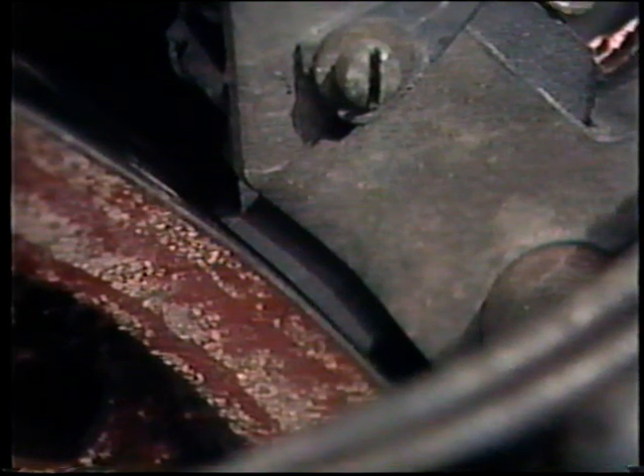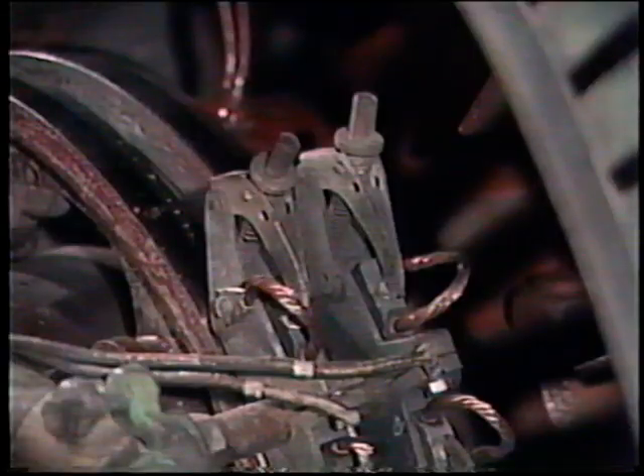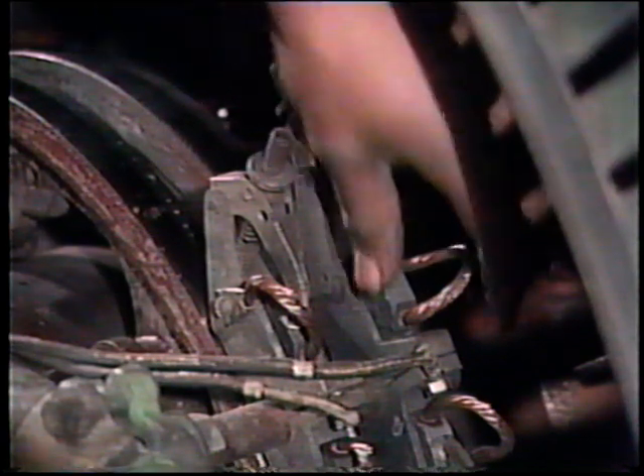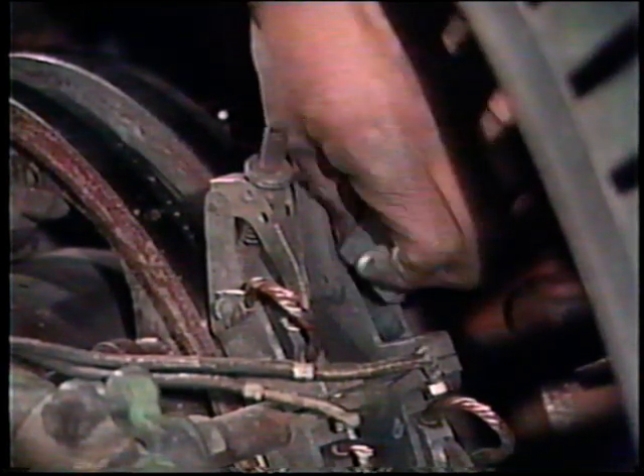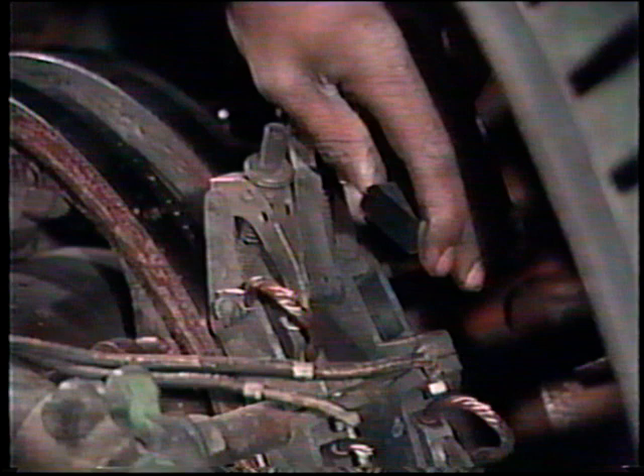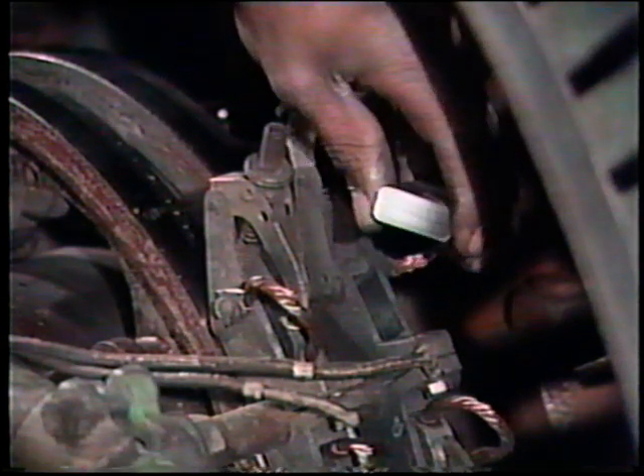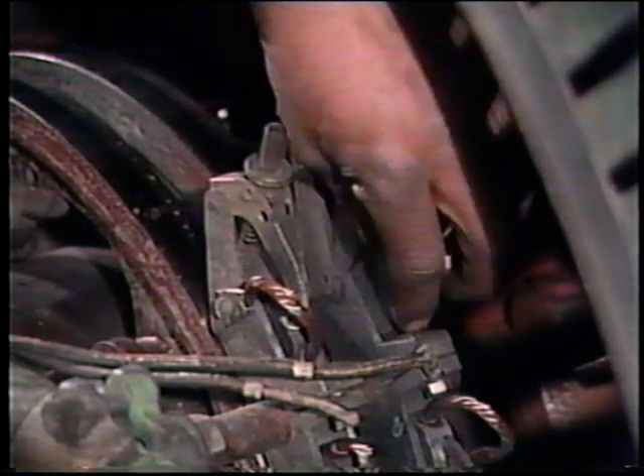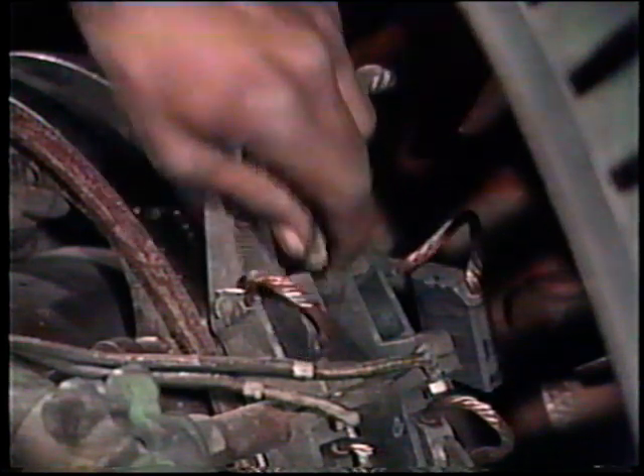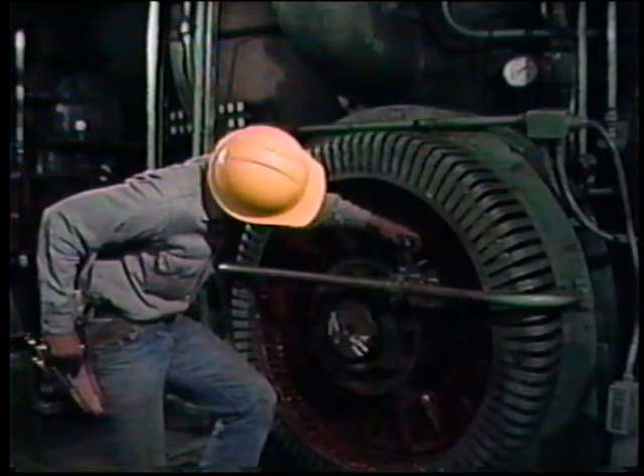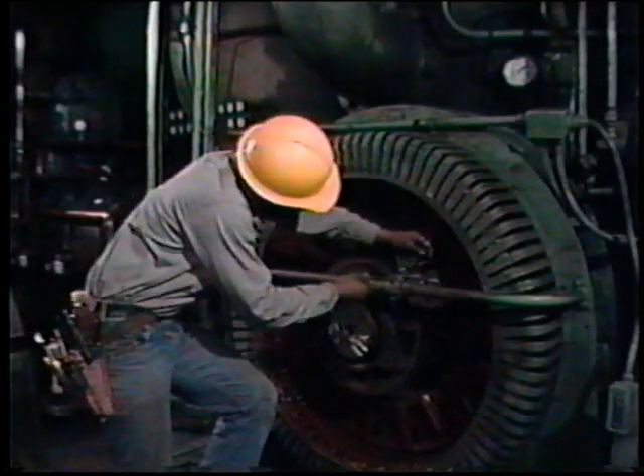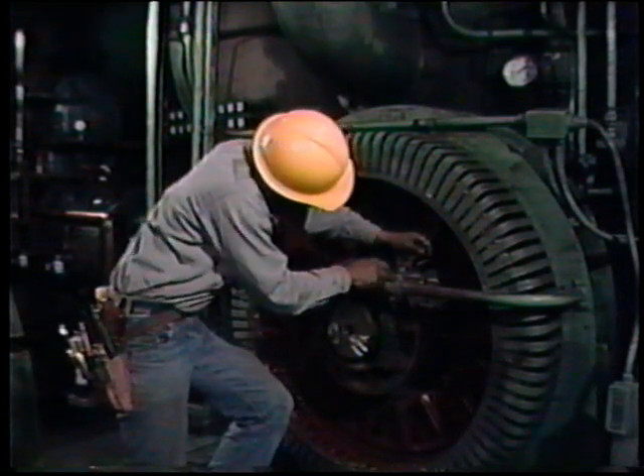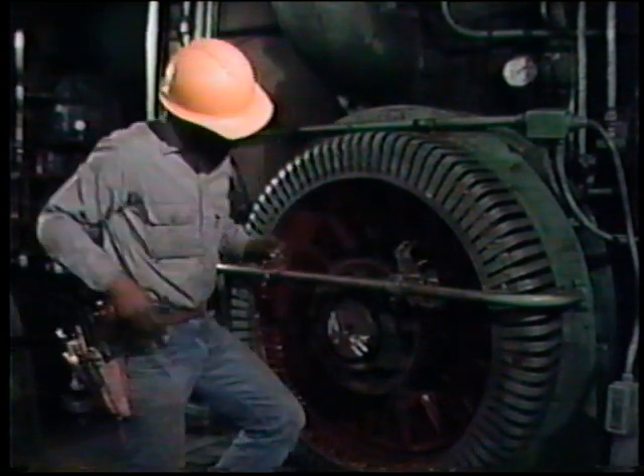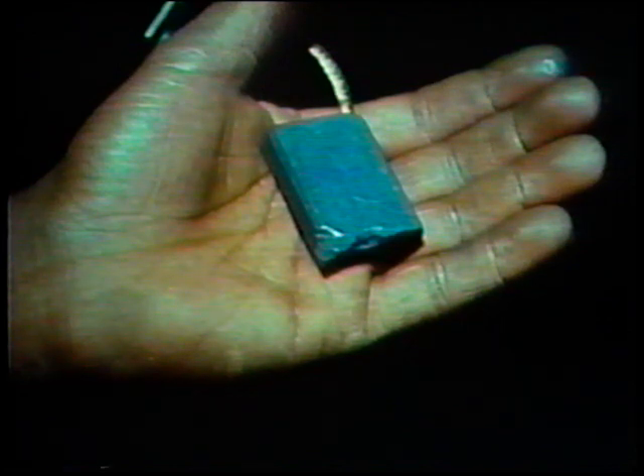Make sure all the brushes touch their slip rings and are properly seated. Remove the brushes and carefully examine them for grooving, chipping, or any other signs that might indicate a problem. If you find a problem, loosen the brush's electrical connection and the brush can be removed from its holder. This brush is chipped, so it's necessary to replace it.